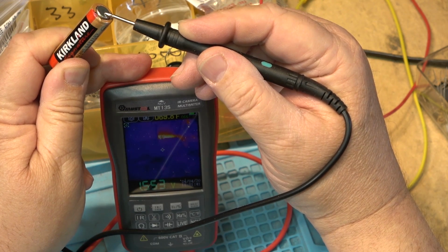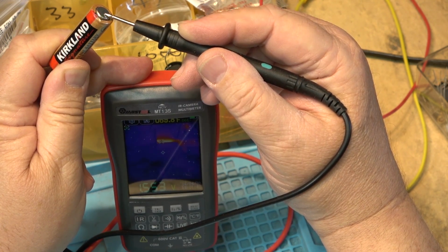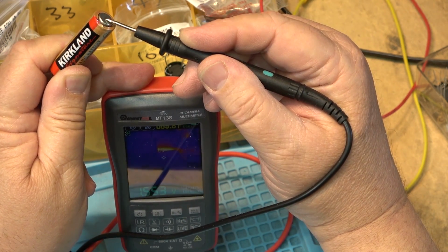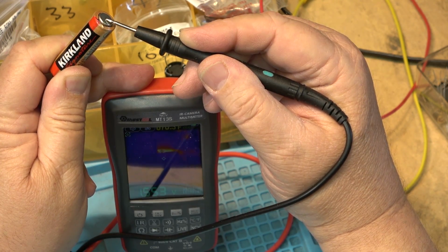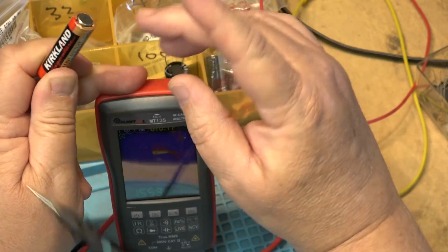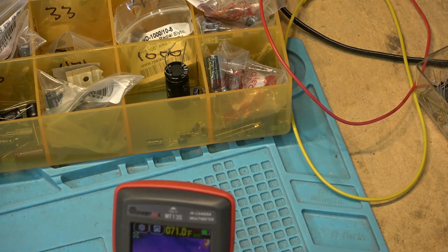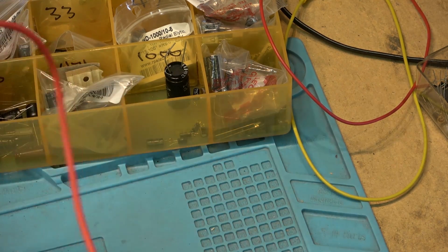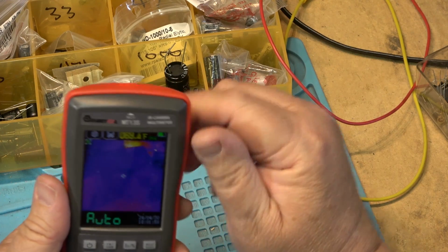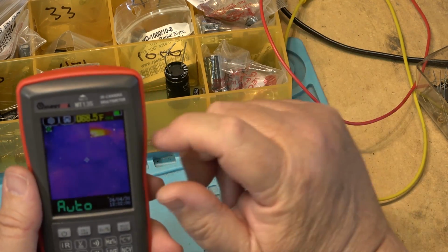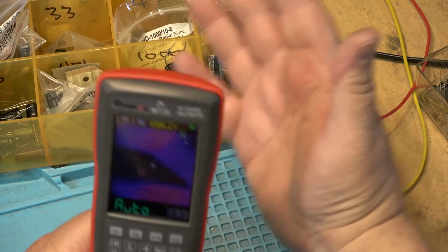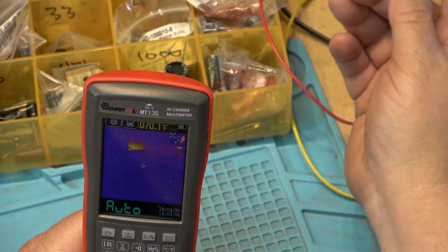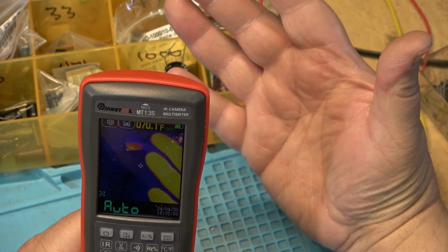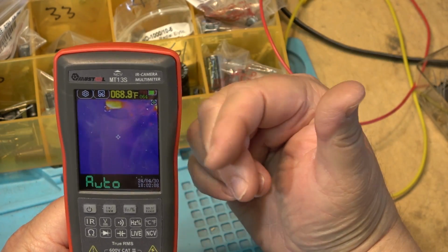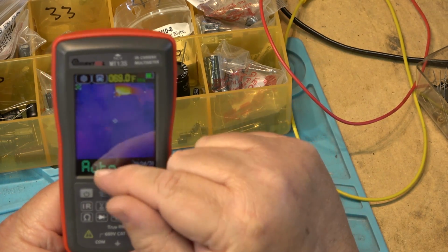So yes, I can measure voltage at the same time as I'm looking at the infrared camera on one device. How cool is that? That's pretty cool, if you ask me. So you can use the thermal camera for looking for a fault while you're monitoring the voltage on the same tool. Monitoring something you're turning on, for example, to see if there's a voltage drop and anything's getting hot. You'll see the temperature increasing on the display while watching your voltage.